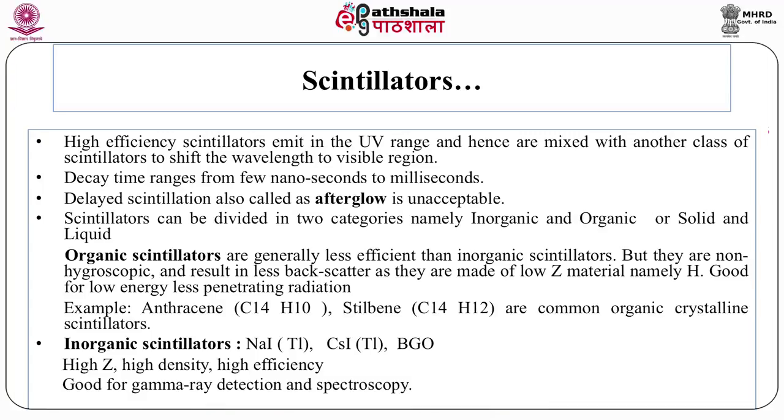Organic scintillators are generally less efficient than inorganic scintillators, but they are not hygroscopic. That means they don't absorb moisture, and they result in less backscatter as they are made of low atomic number material like hydrogen. Good for low energy, less penetrating radiation. For example, anthracene and stilbene are organic crystalline scintillators.